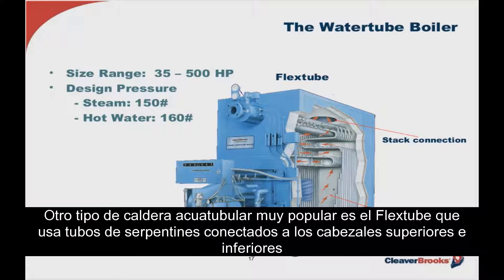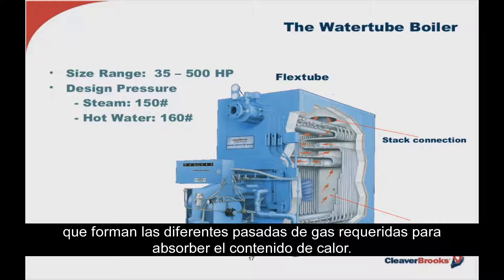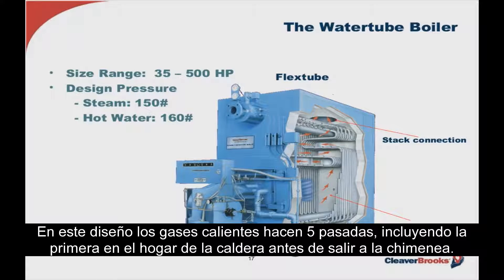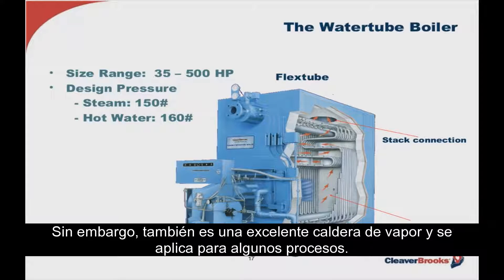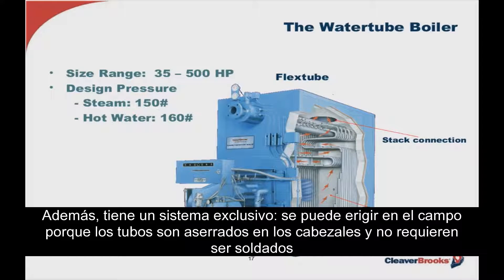The next popular commercial water tube boiler is the flex tube boiler, which uses serpentine tubes connected to upper and lower headers, forming the various gas passes required to absorb the heat contents — the hot gases making five distinct passes including the first pass in the furnace before exiting to the stack. Originally designed primarily for hot water comfort heating as it was resilient to thermal shock, it was also found to be an excellent steam boiler applied in some process applications. It has the ability to be readily field-erected because the tubes are swedged into the respective headers, not requiring any welding.